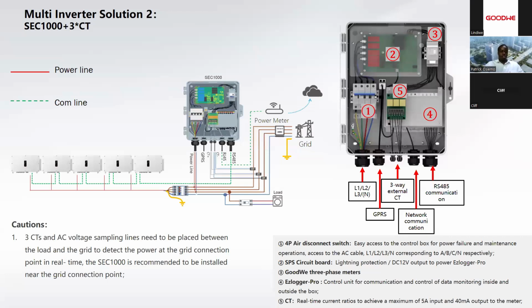With this combination, your inverters and your smart meter will be connecting to the EzLogger Pro, whereas the third-party CTs will be connected to the CT module to let you limit the export power to the grid, as well as monitor the generation of the system and the load. So in your SEMS portal, you'll be able to see the various graphs of the PV generation, how much load you have, and how much is drawn from the grid. That is with the SEC 1000 control box.